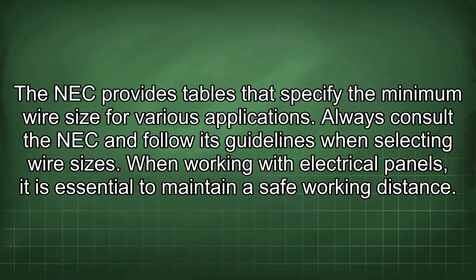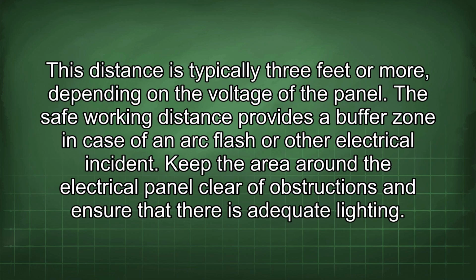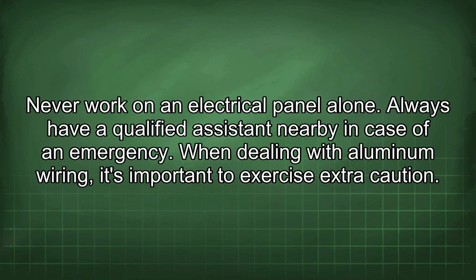When working with electrical panels, it is essential to maintain a safe working distance. This distance is typically 3 feet or more, depending on the voltage of the panel. The safe working distance provides a buffer zone in case of an arc flash or other electrical incident. Keep the area around the electrical panel clear of obstructions and ensure that there is adequate lighting. Never work on an electrical panel alone. Always have a qualified assistant nearby in case of an emergency.